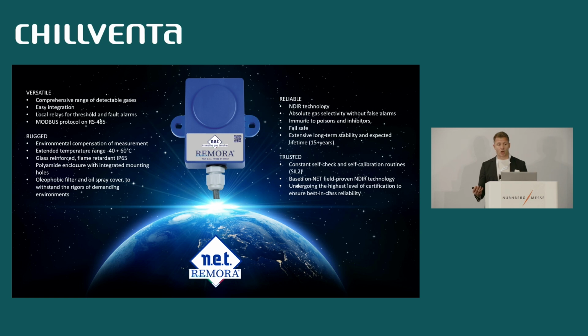Other traditional technologies have problems with chemicals which can poison the sensor. Even high exposure to the target gas can cause the sensor to be poisoned. That doesn't happen with an optical technology. It is fail-safe. That means the sensor cannot go in a state where it becomes unresponsive to the target gas without you knowing it. The sensor will always inform you about any fault or alarm condition.